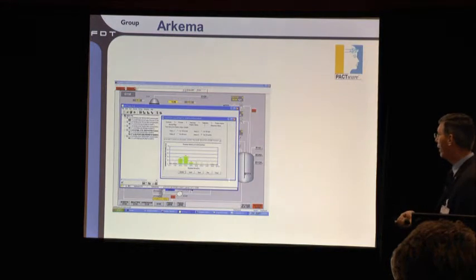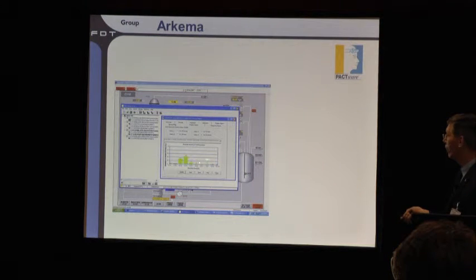These red bars show where it's starting to require too much force for the effort involved in positioning that valve. The more it shows up in the red zones, the more concerning - but you can see the vast majority is within an acceptable range, so this valve is probably in pretty good shape, as reported by the positioner at this point.